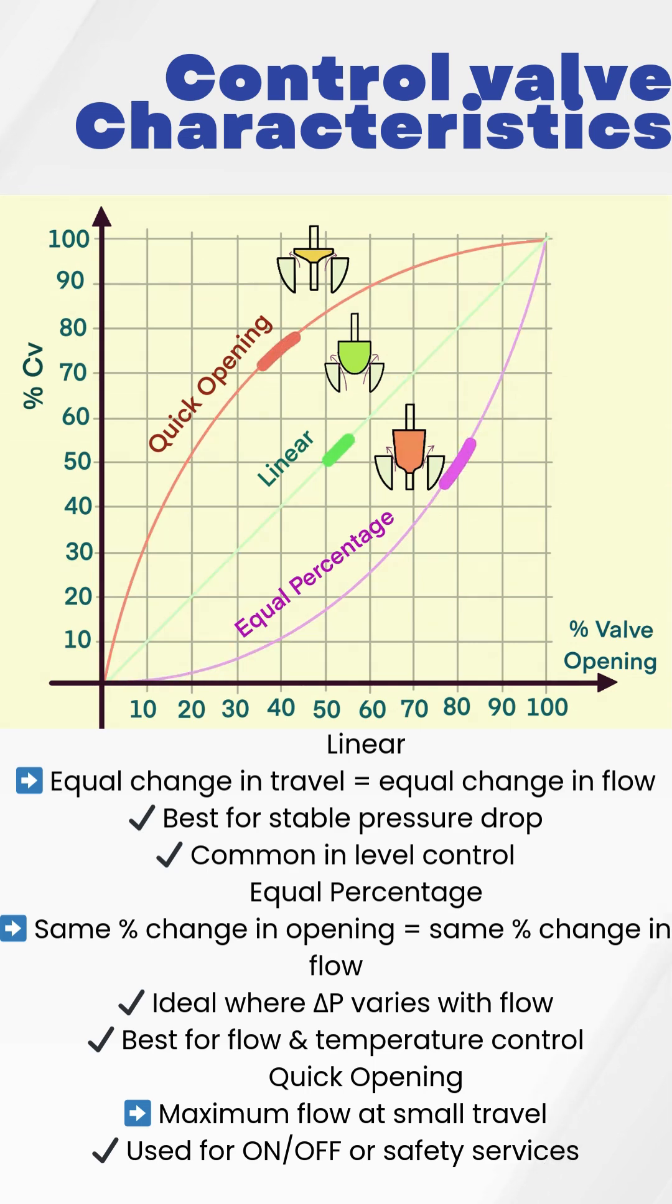If pressure drop is constant and control range is narrow, choose linear. For shutdown or interlock services, quick opening is the right option.